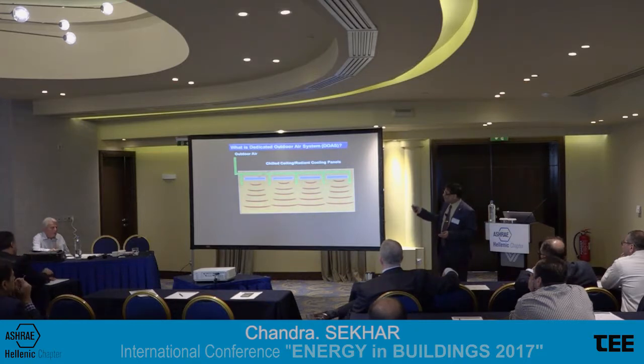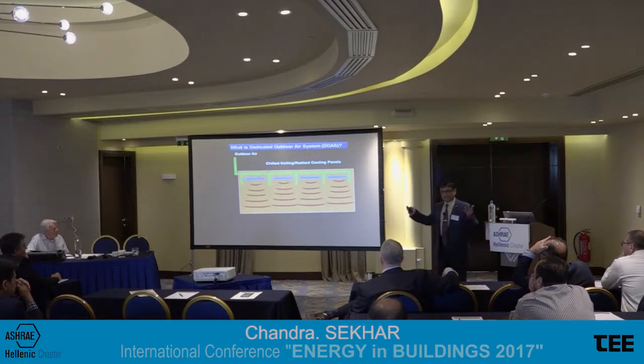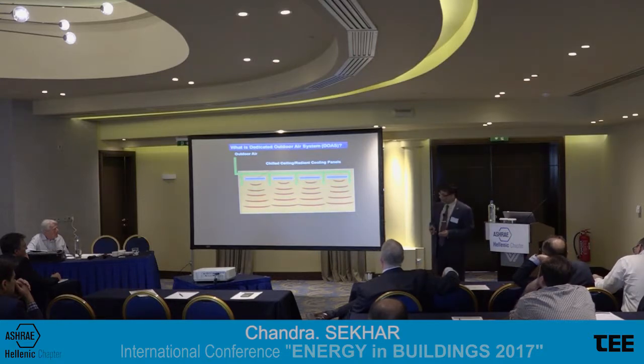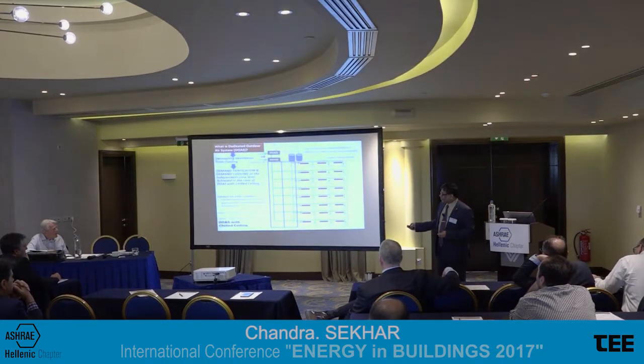You could be looking at something like combining a DOAS concept with chilled ceiling - radiant cooling panels, as I'm sure you've heard about. Chilled beam is another concept, where we separate the sensible cooling part of what we need to do in the buildings or occupied zones. So, DOAS with chilled ceiling, DOAS with chilled beam.